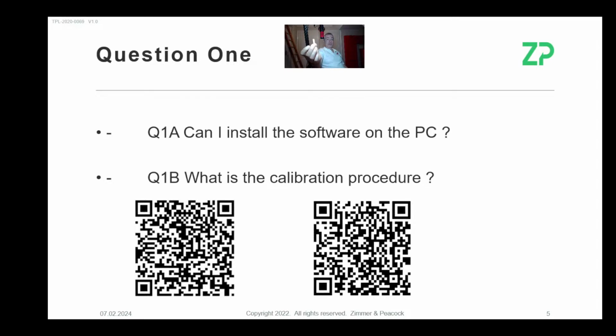It's our repeatability of manufacturing that means you don't need to calibrate in the field. If you can manufacture these in a repeatable manner, then you can essentially qualify the batch, release it to the market, and people can use them. So we do that to ensure the product is going to work and that there is no calibration. When people ask about calibration, it's because they're thinking about traditional lab instruments with a PC. In fact, I'll talk about HPLC in a bit, which does require calibration. So this is much more of a consumer, app-driven, non-PC system, which doesn't require calibration. Let me fast forward a little bit, because ZP is really coming from an IVD blood testing world where you don't need that.